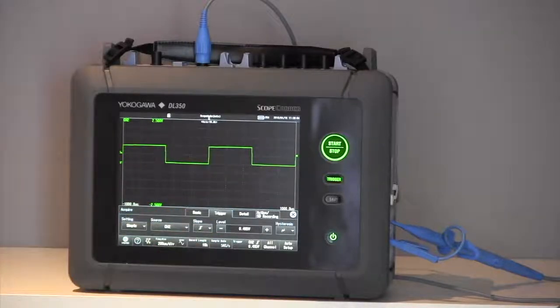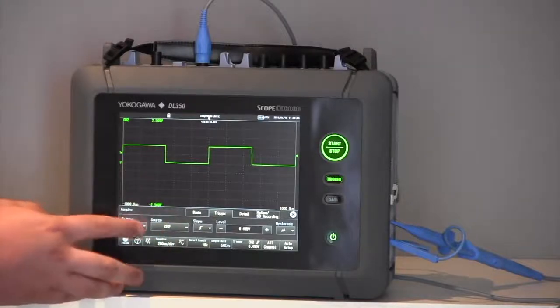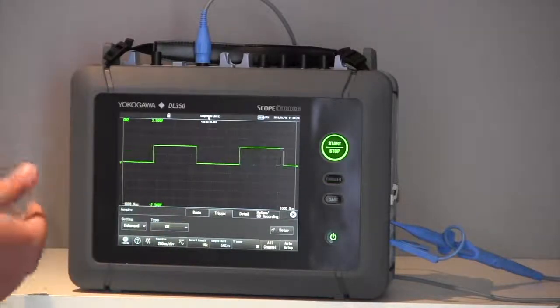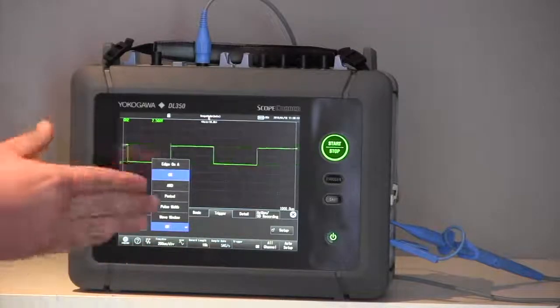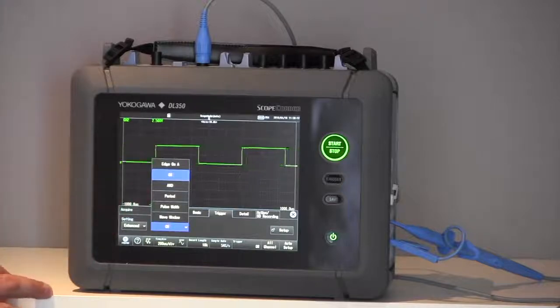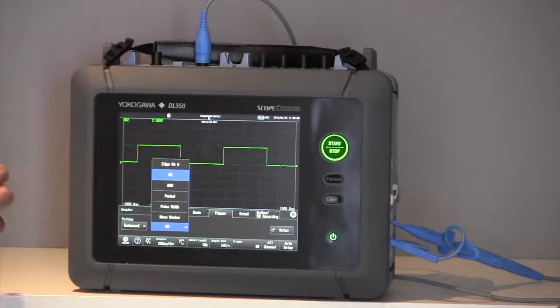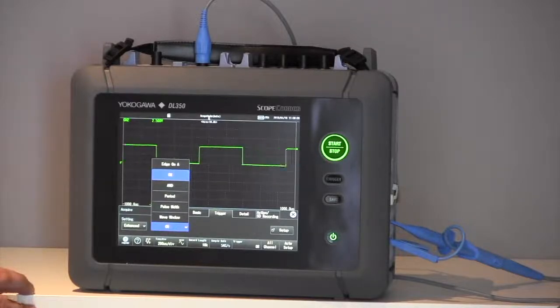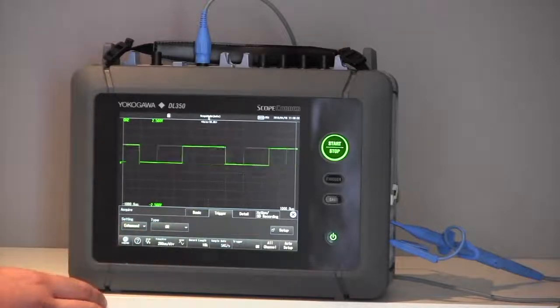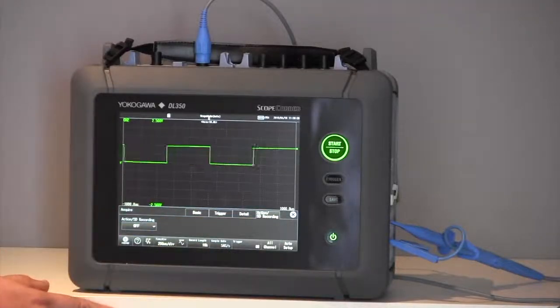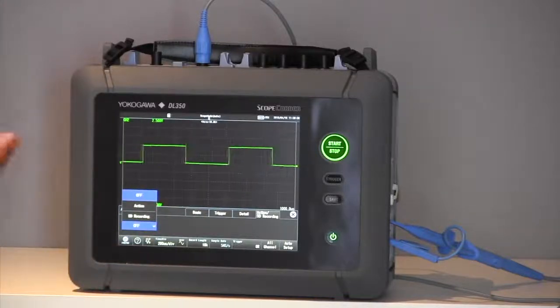Also here we have triggering menus where we have simple rising edge, falling edge triggering. We also have enhanced triggering, which is and or triggering as well. We can also do what's called a wave window trigger. So suppose I have a stable signal, I can put an upper and lower limit around that stable signal, and should there be a voltage dropout, should there be a transient event, a spike, an overshoot, we can capture and record all of those events as well. Finally, on the triggering, we have what is called action on triggering. Action on triggering allows me to output a signal in the event of a triggered event. The ScopeCorder could beep at me, and there are other features which come with the action on trigger as well.